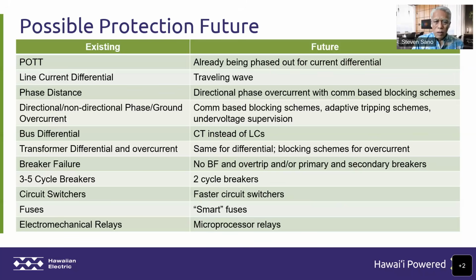Again, with the decrease in fault overcurrent levels, we believe that overcurrent schemes can still work, but they'll have to be supplemented with communication, which we don't currently have, adaptive type tripping schemes, and undervoltage supervision. So, we believe they can work, but they will require supplemental elements to be added to them.